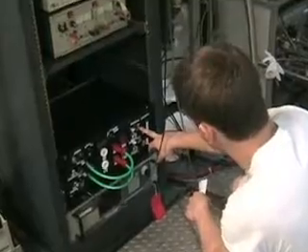And so another thing is this persistent current here on the magnet down here. Whichever magnet you're using, the perpendicular or parallel fields, make sure that you ramp up the heaters on that magnet, so that essentially it unshunts the circuit and allows you to send current down the coil to ramp the field up. So make sure that that's on if you're going to use the magnet.